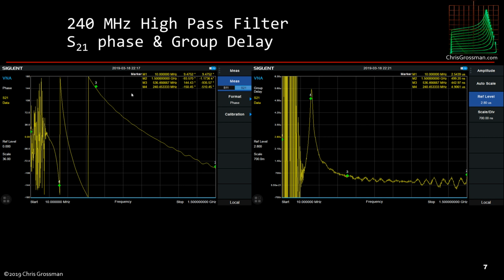Here we're measuring the phase shift of the filter. And if we put a marker on it, we get at that point both the phase on this plus and minus 180 plot, as well as the total phase in degrees, or basically the total delay. These are both very nice things, and when you save the data file, you get both of these. And we can also get the group delay through this filter. This is excellent.